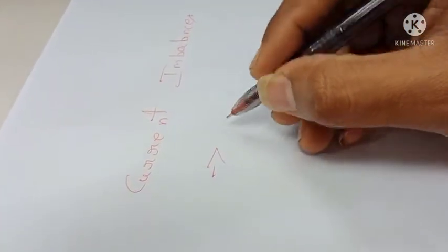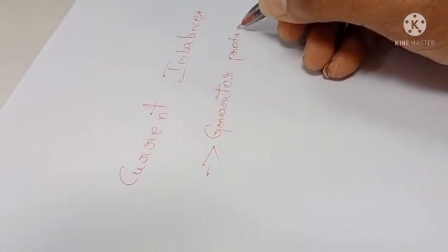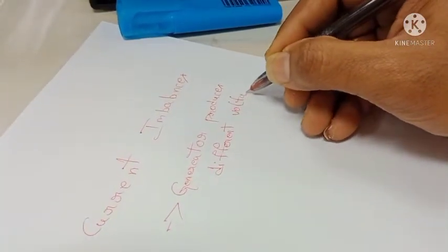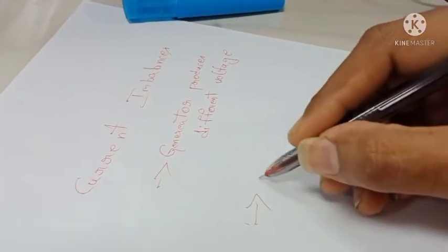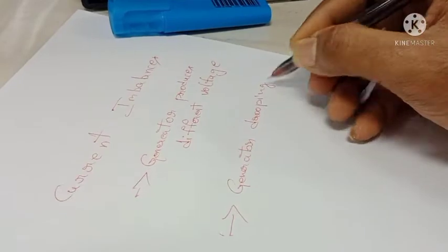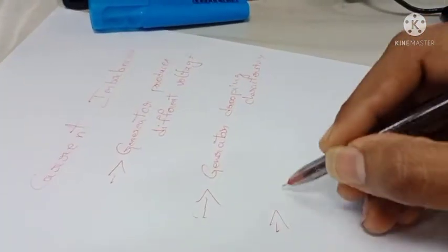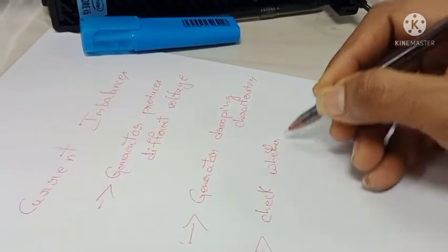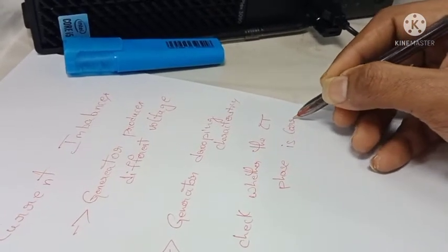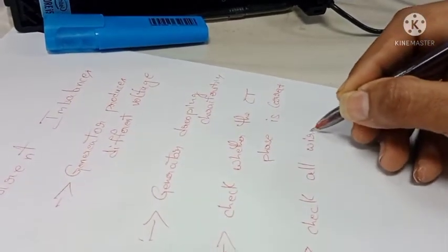These are the troubleshooting points. The first point: check whether the generators are producing different voltages. The second point: check the generator drooping characteristics — compare the characteristics of the generators to see whether all generator behaviors are the same. The third point: check whether the CT phase connections are correct, as they can sometimes be changed during maintenance.